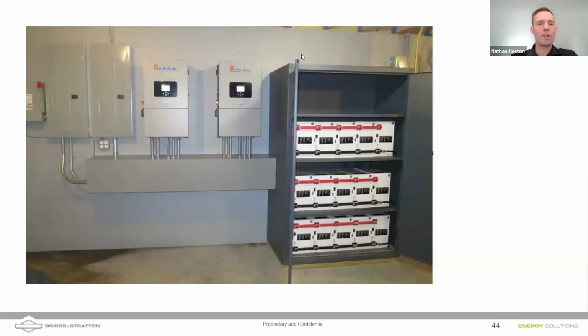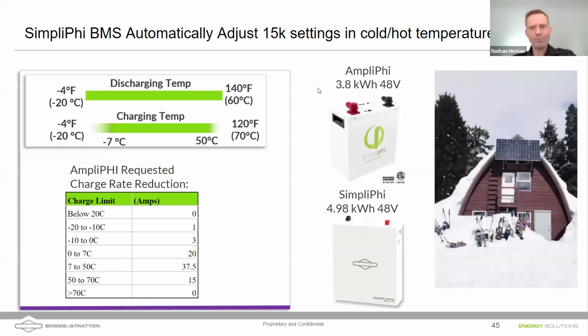Here's a nice example with a couple of, looks like those are 12Ks paralleled together with a larger battery bank. I do want to highlight that our batteries have a built-in temperature system that allows us to use our batteries to lower overall temperatures than most of our competitors. And we do this by using the battery's own internal resistance to heat up those batteries and charge them at slow rates all the way down to negative 20 degrees Celsius.